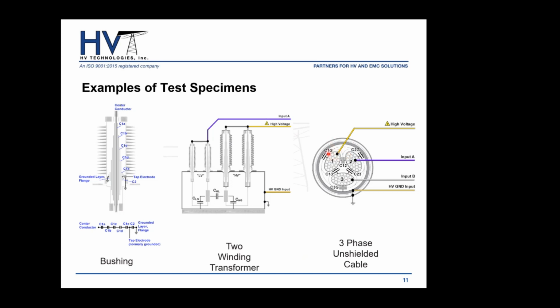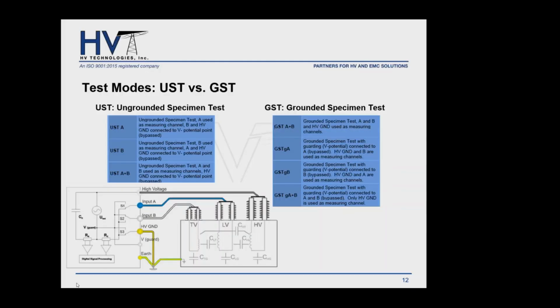I'm sorry, unshielded cable, and then you also have from each individual cable to ground. So you have a total of 6 measurements that you will need, for example, on a 3-phase unshielded cable. So once you identify which capacitances in your specimen you will be trying to measure, then it's very important that we discuss, because as you notice, there are some that are down to ground and some that are not. So it's important to mention the different test modes associated with tan delta and capacitance measurement.